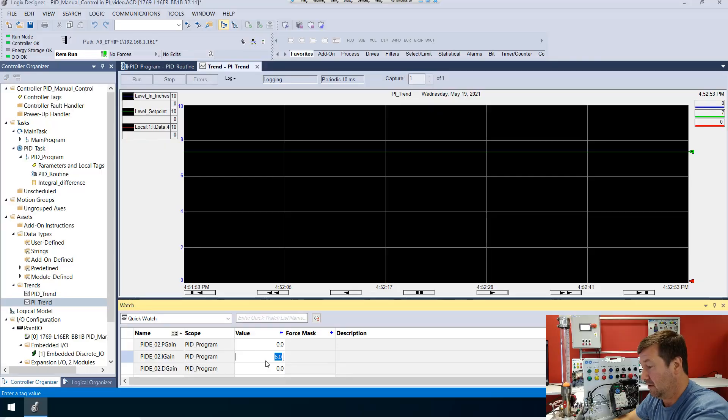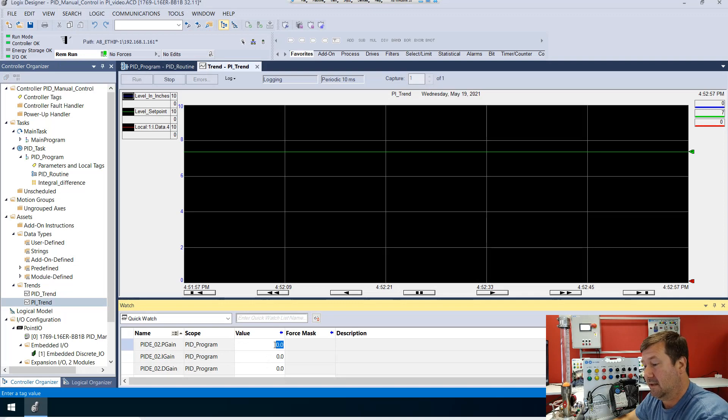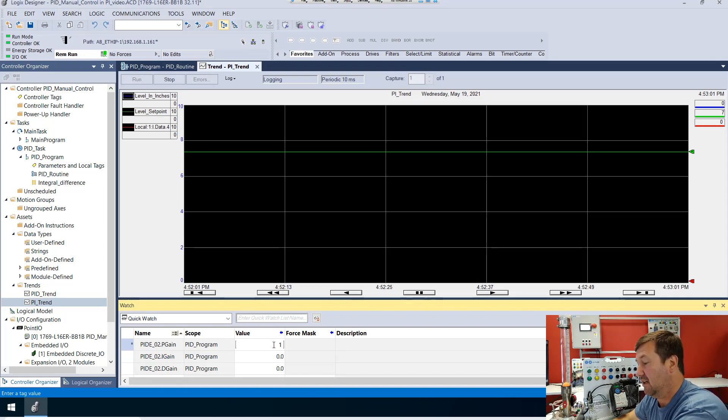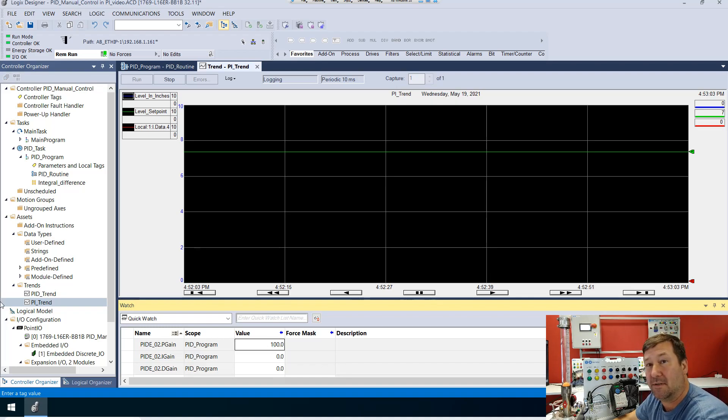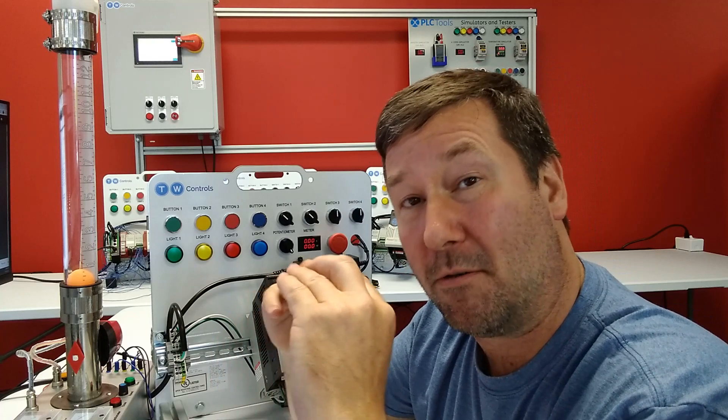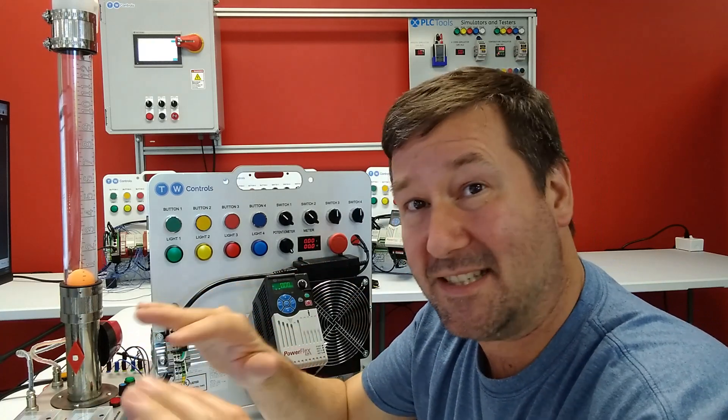Now first, let's kind of bust this myth that you only need the proportional to make the thing run. So we're going to put in a value of zero there, and we're going to put in, I don't know, let's just put in 100 for our proportional. And then we're going to switch switch one on. And you can see our proportional is not really doing anything, even though we've got it cranked way up there. So you cannot really make a PIDE instruction work with just putting in a proportional value. And the reason that people say this is they are looking at a position controlled PID. Allen-Bradley's PID is a velocity controlled PID. And some people who are really super smart with some math can tell you that you can derive one from the other. But that's not where we're going in this video.